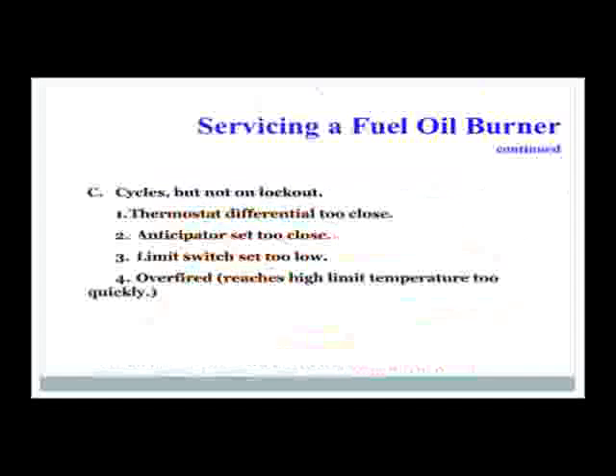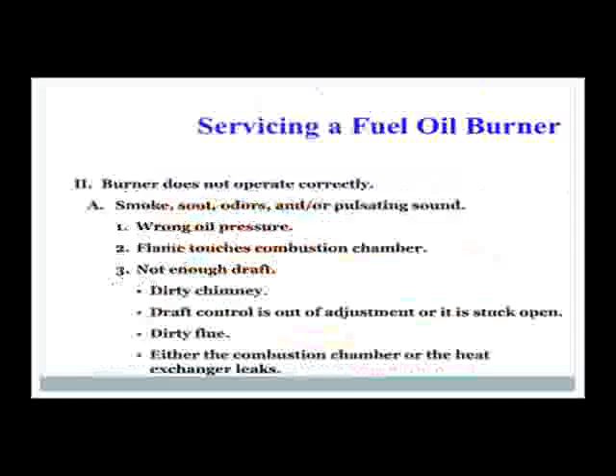If it cycles but doesn't lock out, thermostat differential is too close. Anticipators and limit switches may not be set right. Might have an overfired nozzle as well. If the burner does not operate correctly, you might have soot, smoke, and odors. It could be the wrong oil pressure, could be flame impinging or touching the side of the combustion chamber. You might not have enough draft because of a dirty chimney or draft control being out of adjustment, dirty flues, or combustion or heat exchanger leaks.